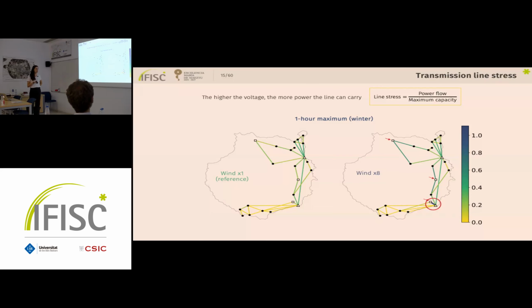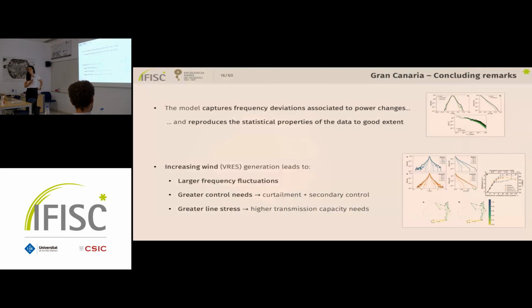So this is something that we have to take into account and probably upgrade the grid in that area. So just to conclude with this part, we have seen that the model we've developed is able to reproduce the statistics of the frequency fluctuations to a good extent. And we have used that model to analyze scenarios with increasing wind generation. And when we do that, we observe larger frequency fluctuations. So we have to increase the control in the system. And we have seen that both curtailment and secondary control are effective at reducing the fluctuations. And we have also seen that the stress of the lines increases. So yeah, there is a higher transmission capacity needs.